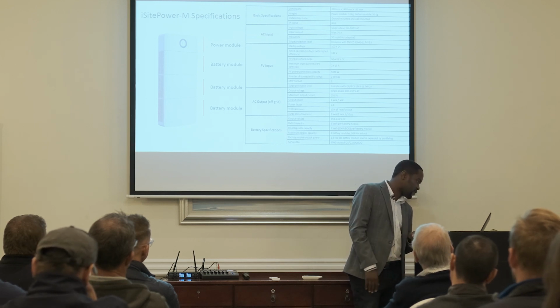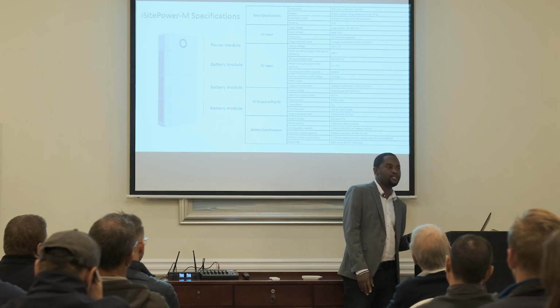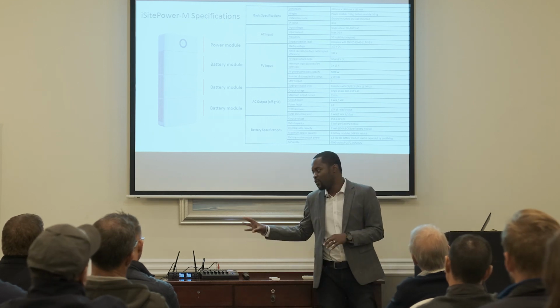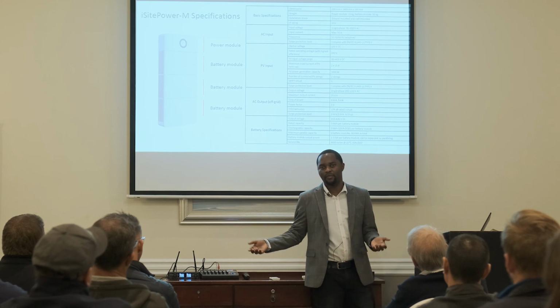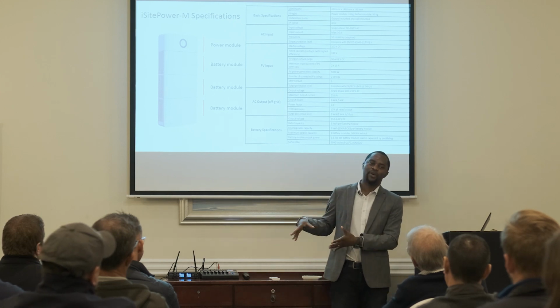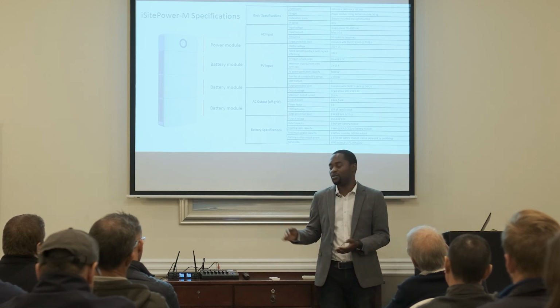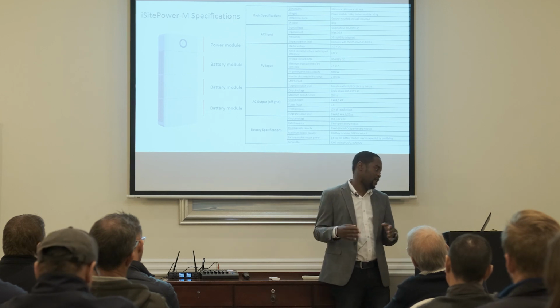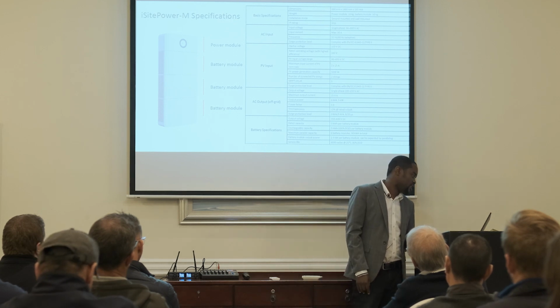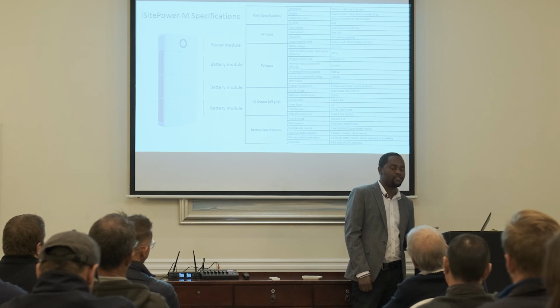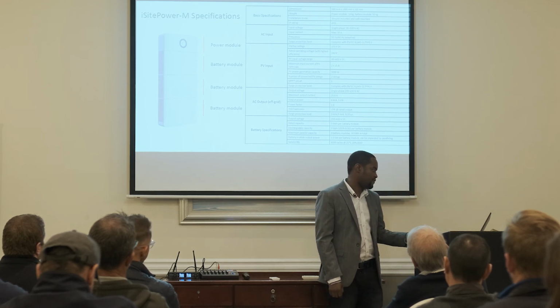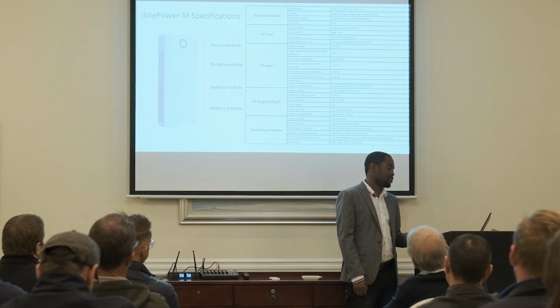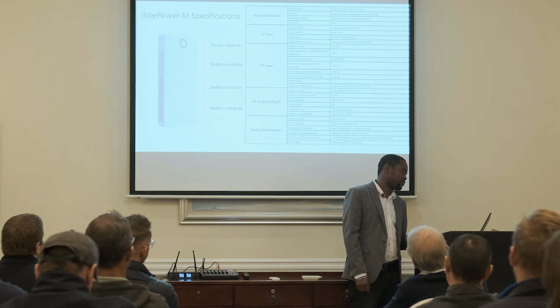Then on the battery specifications, it's a high voltage battery system, right? Then you can't use this Huawei inverter with any other battery. Then you can't use these Huawei batteries with any other inverter. So it needs to be a Huawei battery and also a Huawei inverter. So it's a high voltage battery pack with a voltage range of 350 to 435. Then nominally it's at 400 volts. That's the voltage output that you get from each battery.